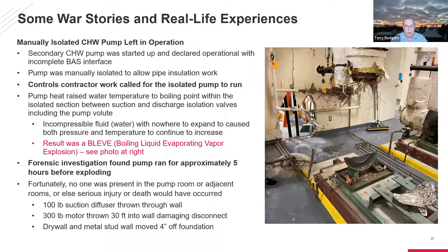And then a flow meter failed. In most cases, if the BMS had been set up correctly, a failed flow meter should have resulted in unreliable data and been taken out of the algorithms and no longer included in the control sequence of operations. In this case, it was just reading 0 GPM. And so the system said we need to start a second pump, and brought the lag pump on, and it still read 0 GPM. So it went to the emergency pump and called it on, and that's how this isolated pump that should never have been operating was commanded to run. And because you didn't have any remote annunciation, nobody realized it. It ran for 5 hours before it finally came unglued.